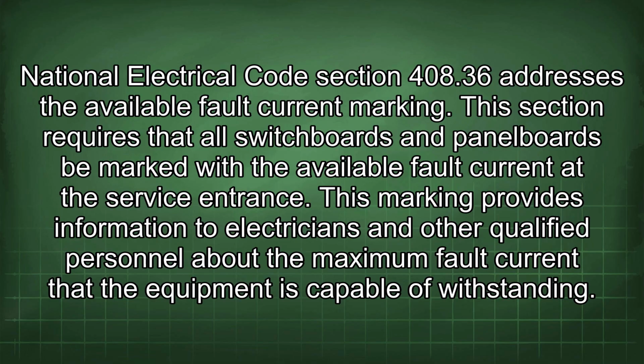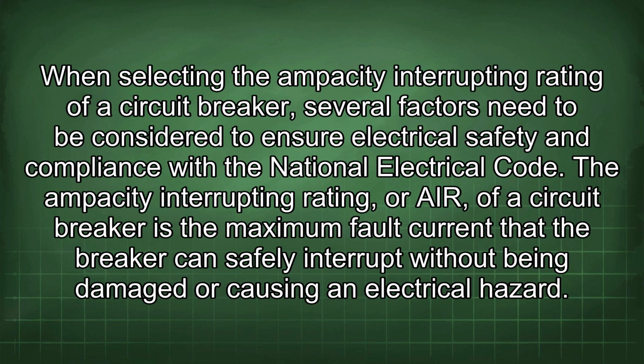of withstanding. When selecting the ampacity interrupting rating of a circuit breaker, several factors need to be considered to ensure electrical safety and compliance with the National Electrical Code. The ampacity interrupting rating, or AIR, of a circuit breaker is the maximum fault current that the breaker can safely interrupt without being damaged or causing an electrical hazard.